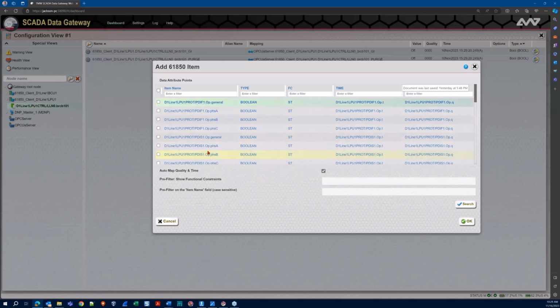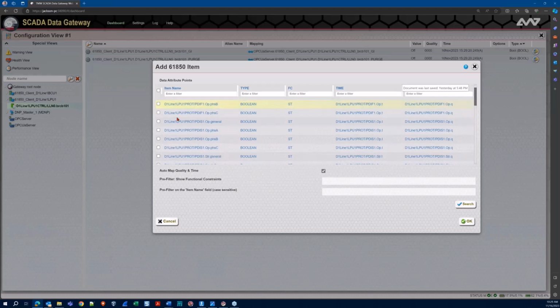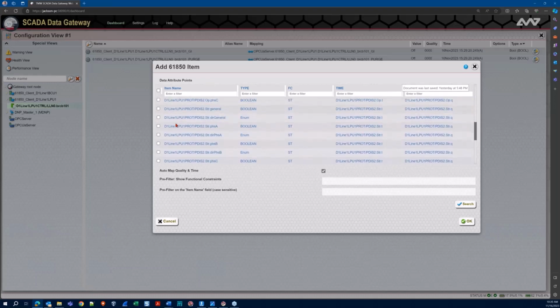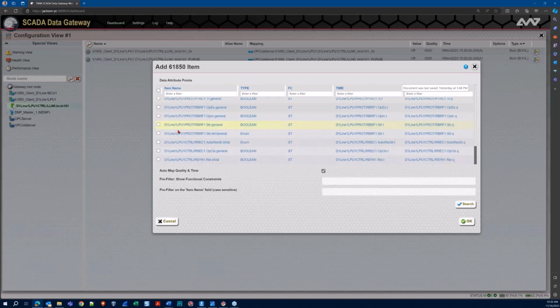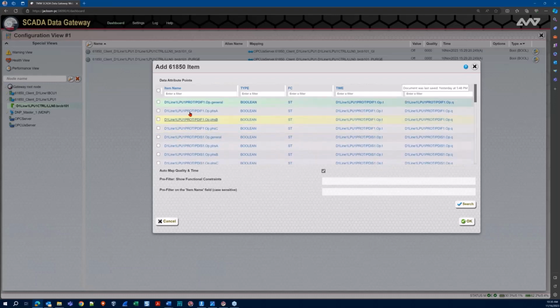It's where I'm adding the data into my gateway of what was made available in that device. I have a couple different options. This is all the data that's available on the device. Each row represents a data attribute in the data set of this particular report control block. I can also see if the timestamp and quality is available, which in this case it is, because they were included at the data object level. I could just add some checks for individual ones that I want to add.